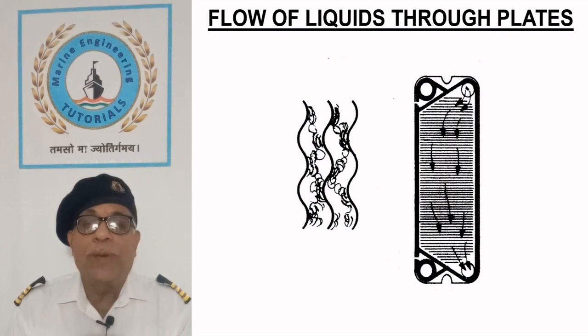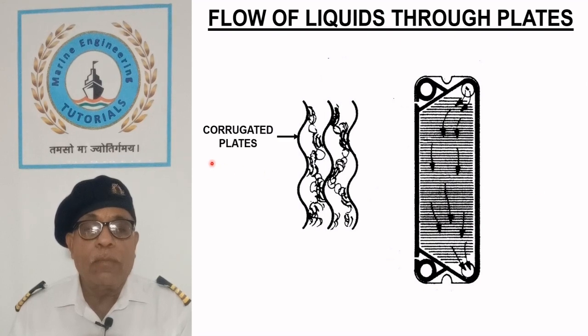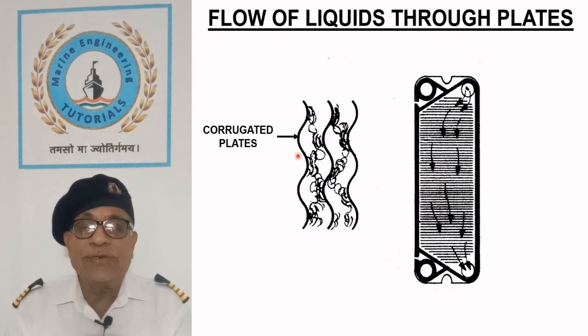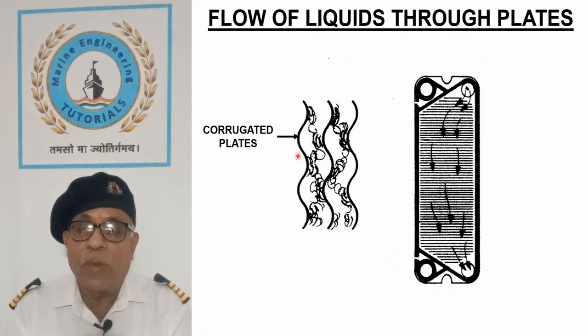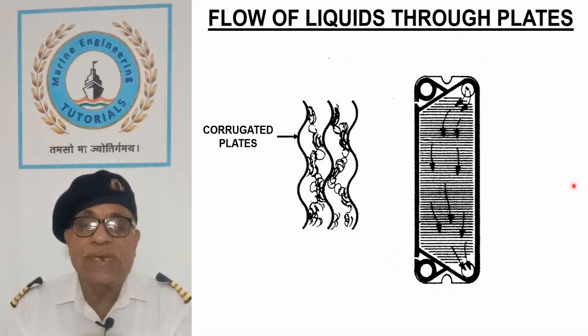Flow of liquids through plates. This sketch describes the construction of plates with their sealing arrangement and the flow of liquids through them. The plates are corrugated as shown in the sketch, which makes them stiff, so they require less thickness. Corrugations additionally increase the surface area. Both the increased surface area and reduced plate thickness improve heat exchange efficiency.